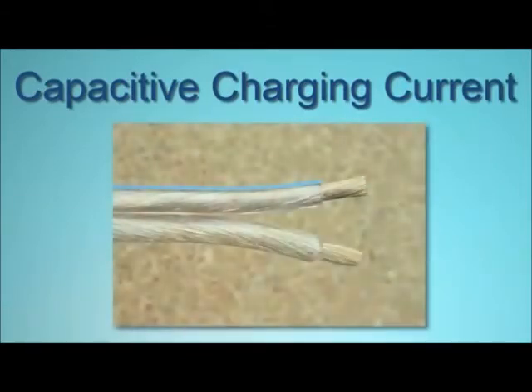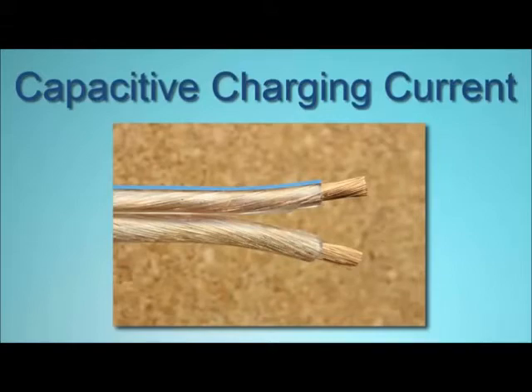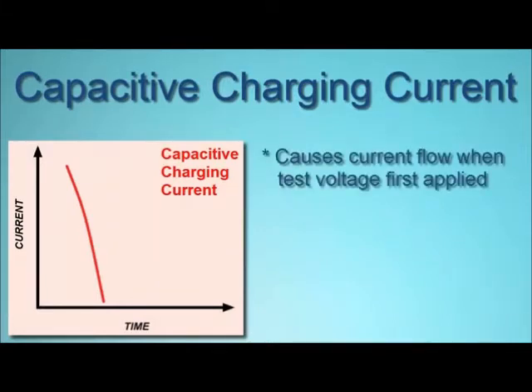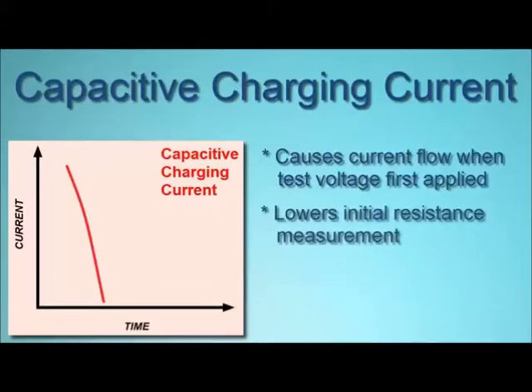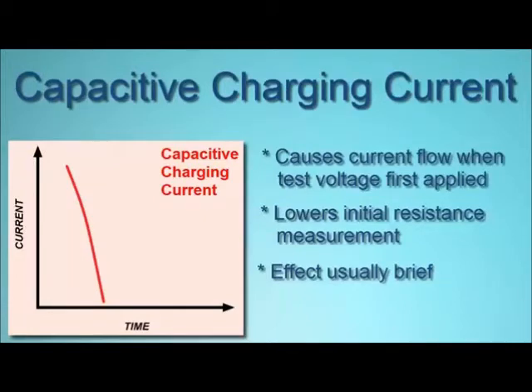When two conductors are in close proximity separated by an insulator — for example, a length of common two-wire electrical cord — they can act as a capacitor. When test voltage is first applied, this capacitive charging effect results in current briefly flowing through the conductors until the voltage across the insulation reaches the test voltage. Consequently, the initial resistance measurement will be relatively low and then quickly rise as the capacitance becomes fully charged. This effect is usually brief, often lasting less than a second, although in very long cables or large motors this can last much longer, up to 30 minutes or more. Capacitive charging current is not an indicator of insulation quality, but it needs to be accounted for to assure your measurement is meaningful and relevant.